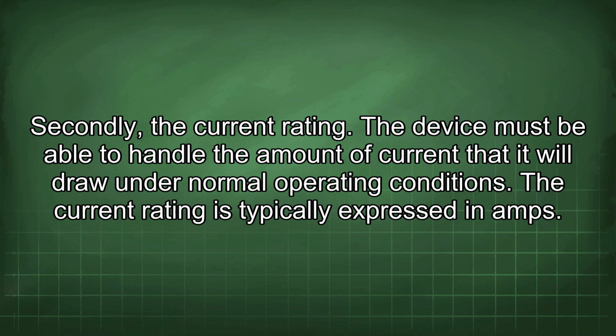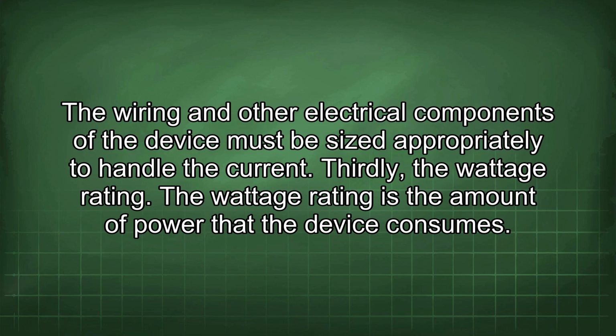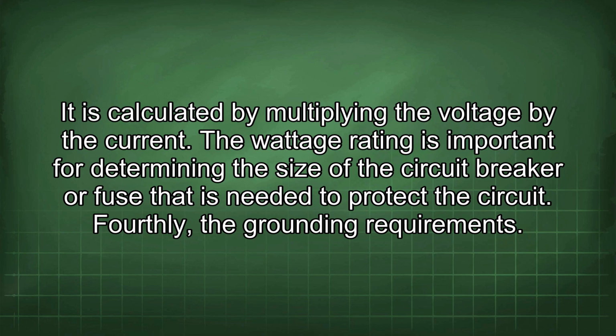Secondly, the current rating. The device must be able to handle the amount of current that it will draw under normal operating conditions. The current rating is typically expressed in amps. The wiring and other electrical components of the device must be sized appropriately to handle the current. Thirdly, the wattage rating. The wattage rating is the amount of power that the device consumes. It is calculated by multiplying the voltage by the current. The wattage rating is important for determining the size of the circuit breaker or fuse that is needed to protect the circuit.